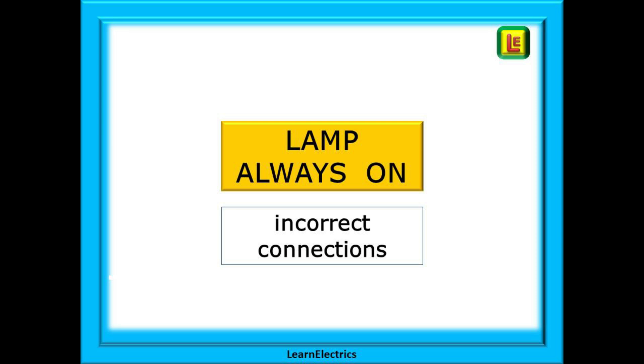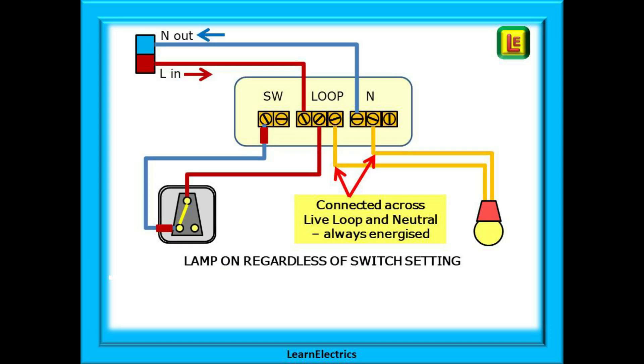Let's have an opposite scenario now — the lamp is always on. Again, a result of incorrect terminations. Compare this to the good example from a few slides ago. Someone in their wisdom has connected the lamp wires between the live loop and the neutral blocks. This means that the switch has been bypassed and the lamp is permanently energised — it will never turn off. To restore order, move the lamp wire from the live loop block to the empty hole in the switch block.